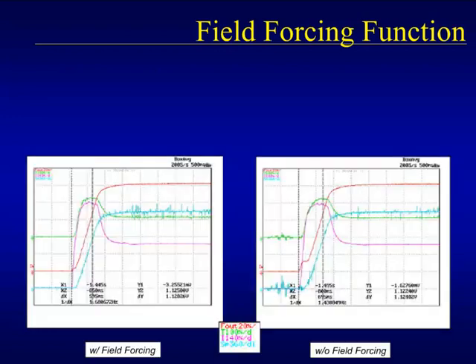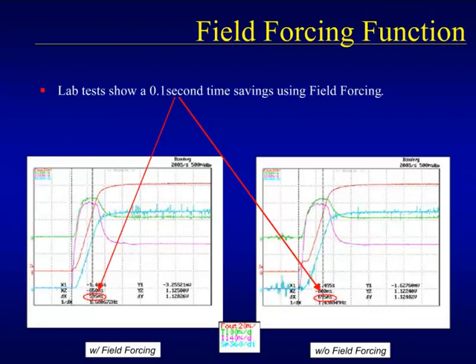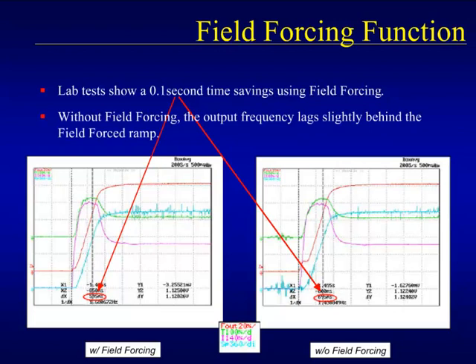These scope trace captures are from a test stand that was accelerated with and without field forcing. The motor in question was a 15 horsepower motor, and field forcing showed a 100 millisecond improvement in acceleration. The non-field force trace lags behind the field force one due to the time it takes to build up the flux in the motor, which in turn affects the ramp. Remember, the larger the motor, the greater the benefit of field forcing.